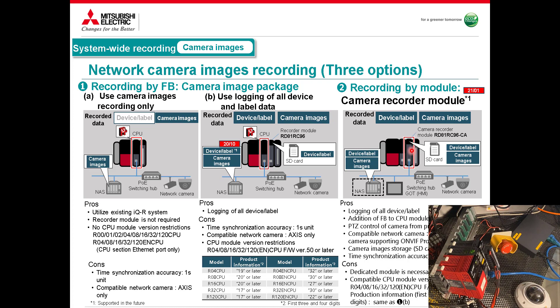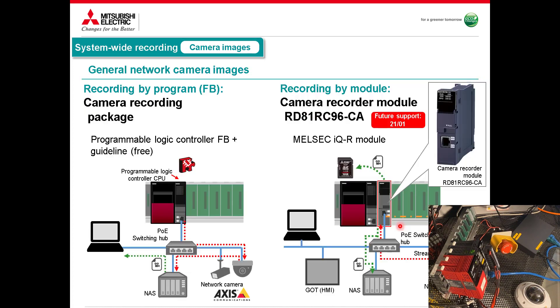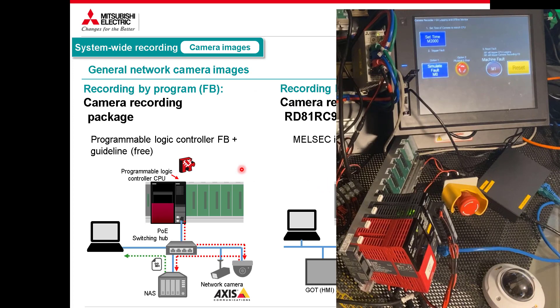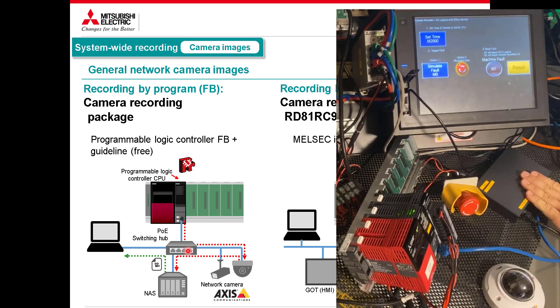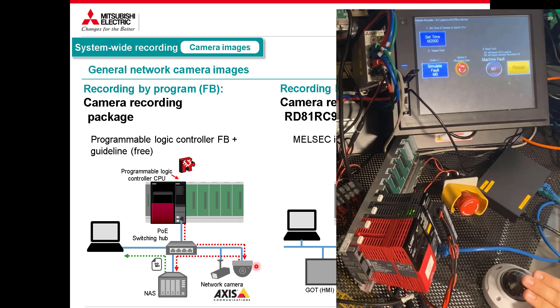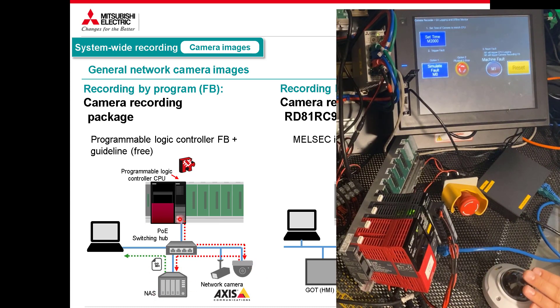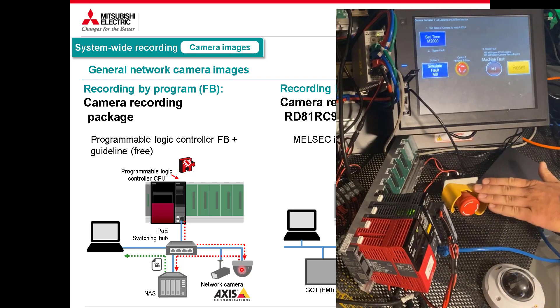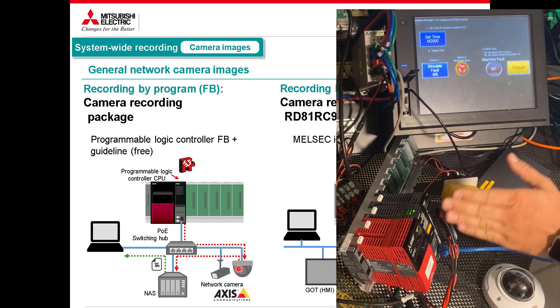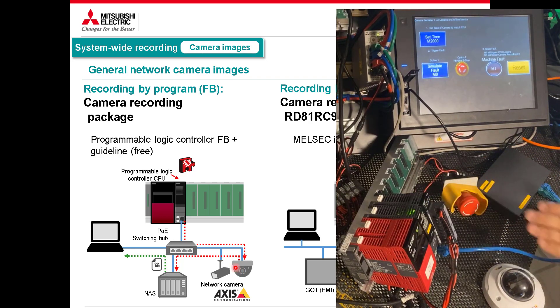The benefit of having everything in one central location is it makes it much easier to compare what was going on with the video feed to what was going on in logic. Looking at a blown-up view: we have a standard CPU, a PoE switch running to an Axis camera, and storage on my PC. The CPU will be time-synced with the camera and tell it when to record. I've got an E-stop wired in — not a safety stop, just a standard input — so when I press the E-stop we should get a fault.